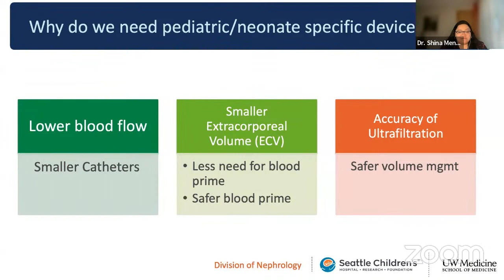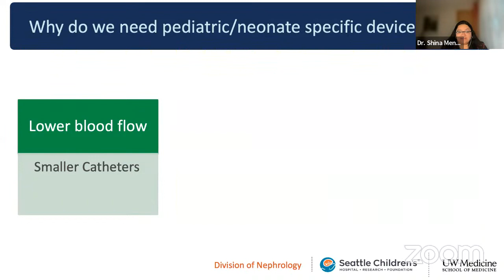So yeah, why do we need smaller devices? Because babies are small. We require smaller catheters, we are trying to avoid blood prime in these babies, and we want more accurate devices. So let's look at what these devices are and what the blood flows are. This table tries to summarize the available devices, and you can see, depending on whether it's a neonate specific device or an adapted device, the blood flow can range anywhere from a lower end of 2 mLs per minute, or 5 mLs per minute for NIDUS, all the way up to 50 to 200 mLs per minute for an M60 filter.